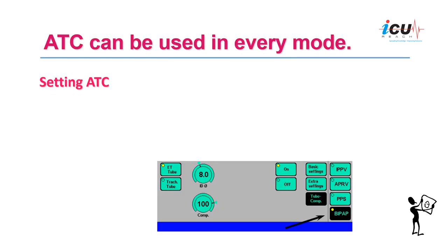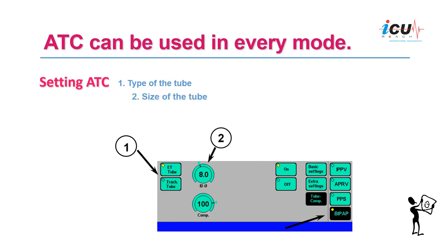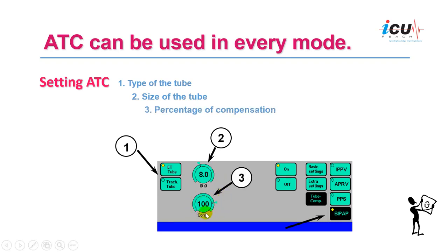To set up ATC, you first need to know the type of tube — whether it is an endotracheal tube or a tracheostomy tube — and then the size of the tube. You enter these on the ventilator and then determine the percentage of compensation, whether you compensate for 80 percent or 100 percent. Once set, you switch it on.